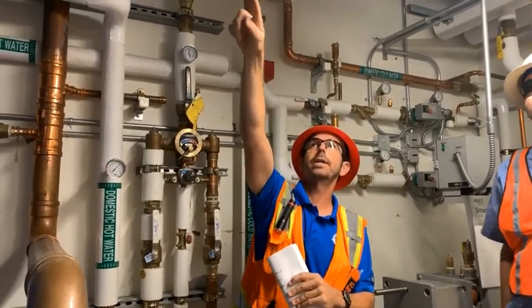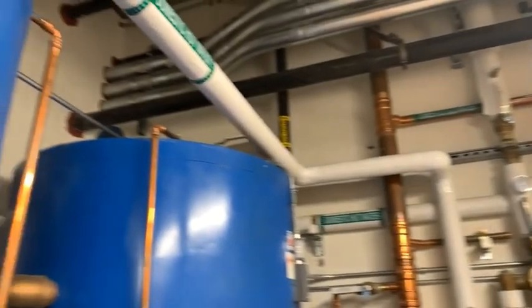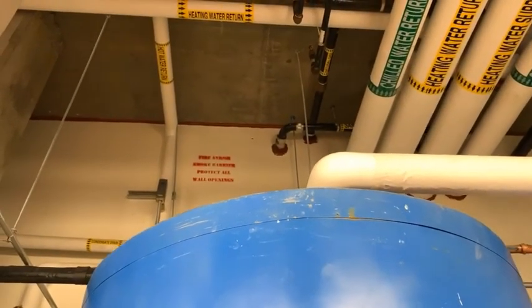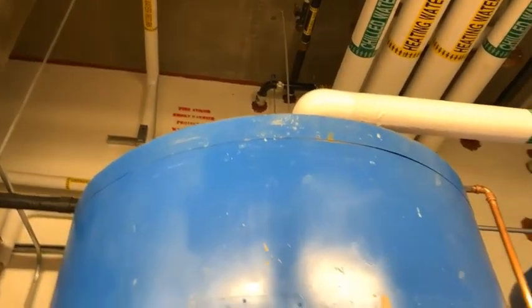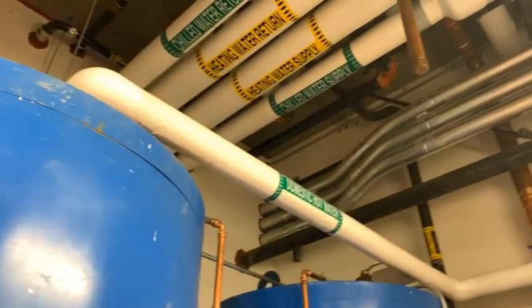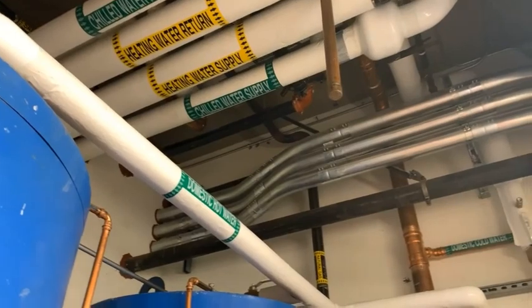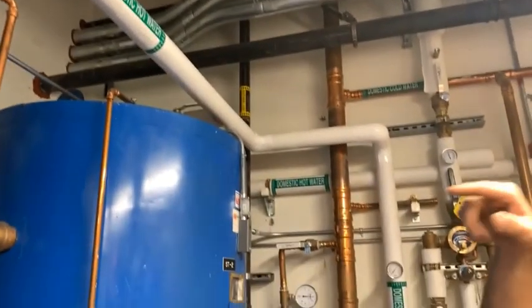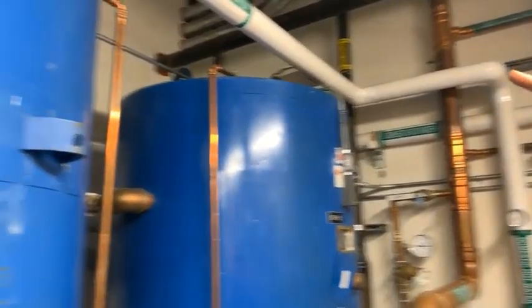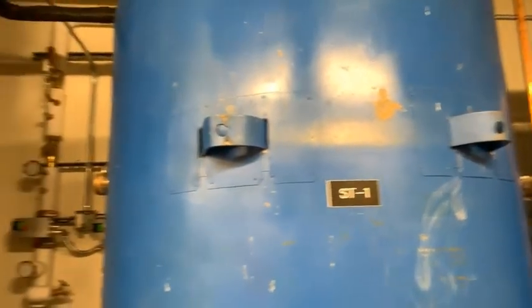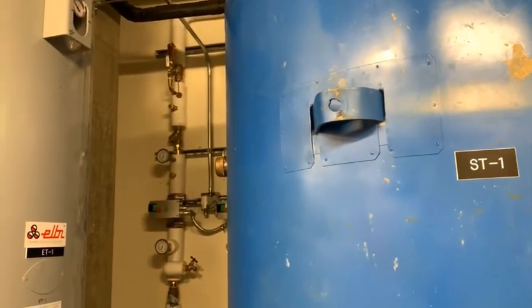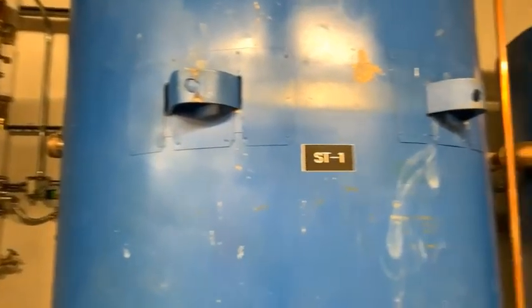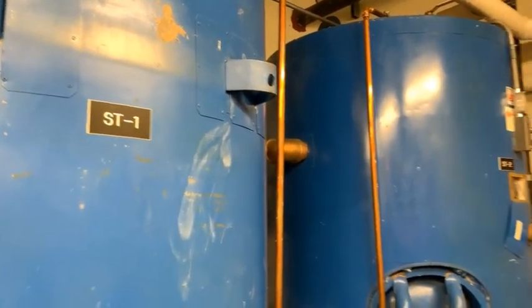It's gonna start behind us. There's a pipe up here that says hot water return. It's gonna come down, there's an aquastat, and it'll go through 2 circ pumps. The circ pumps are redundant, so only one will work. We have training on that tomorrow. They're twinned together real quick, so only one works. There's a master and a slave. The master will tell which one to run, depending if the aquastat's calling for the pumps to run, okay? But that water comes back.